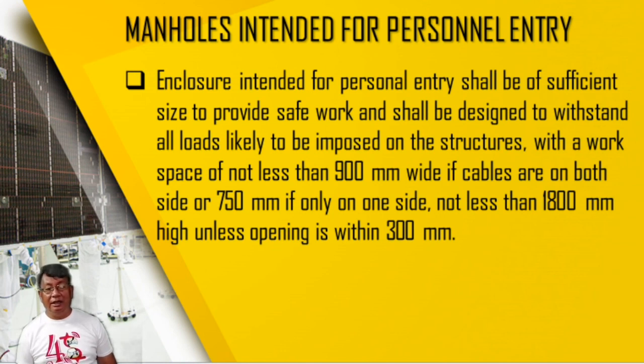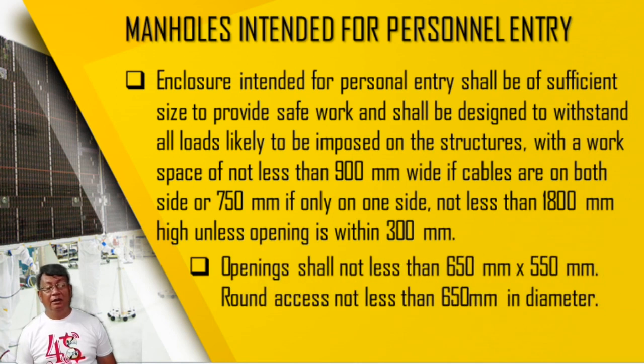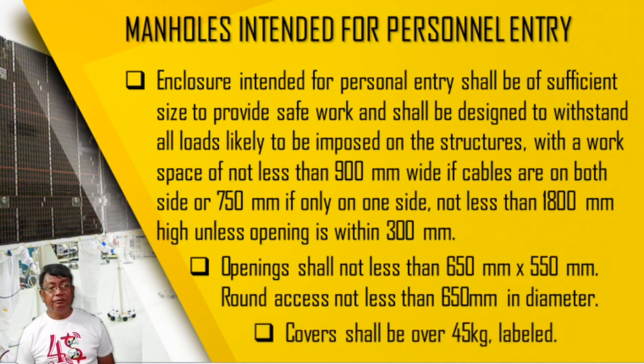Unless the opening is within 300 mm, the opening shall be not less than 650 by 550 millimeter, or not less than 650 millimeter in diameter if it is round. So that is your manhole. Now, why do we specify this diameter or opening? Because it is very clear that for the worker, the electrician, the installer, we need efficient distances for safe work. Then a cover over 45 kilograms shall be labeled. So if the cover of the manhole is over 45 kilograms, then it should be labeled.